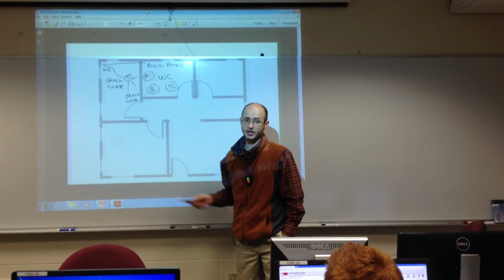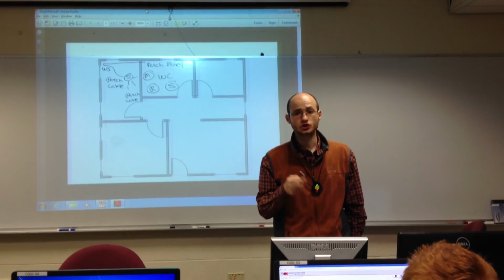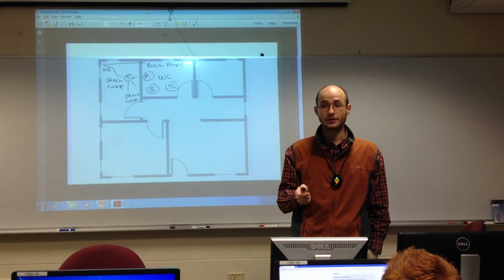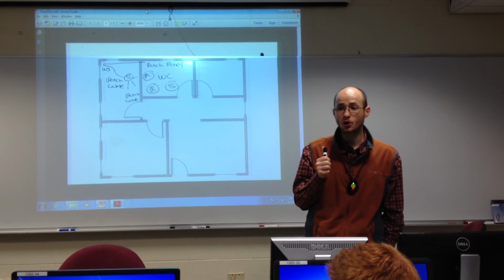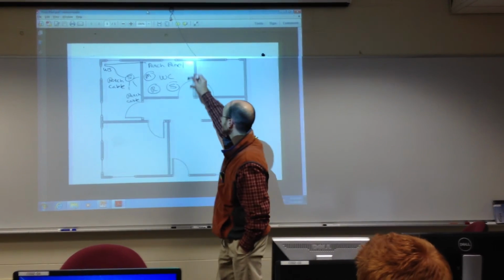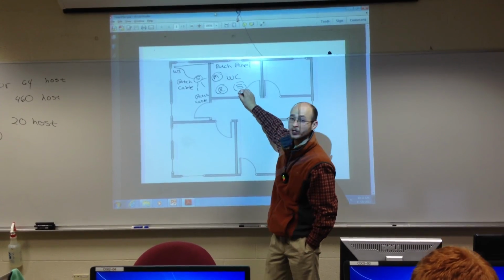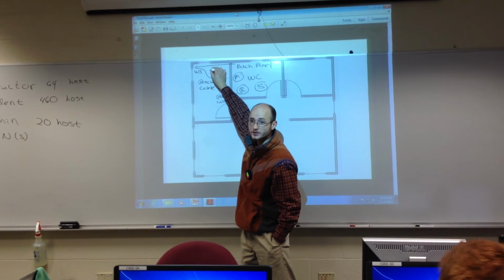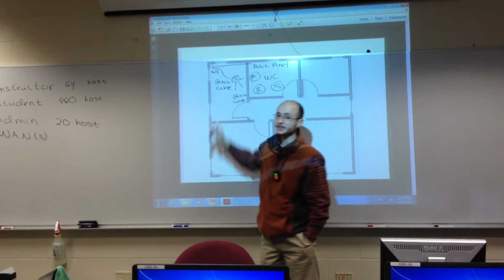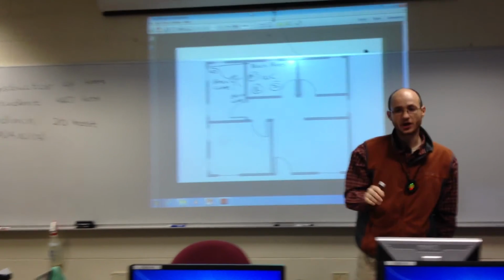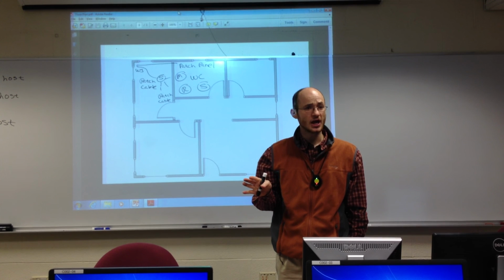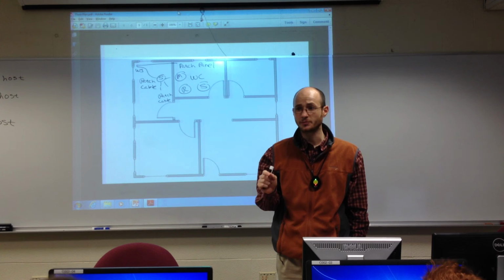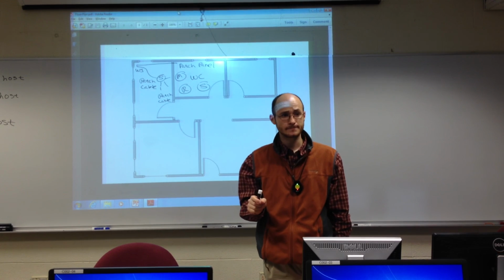So what do we gain by putting a wiring closet on every floor? Shorter horizontal runs. More work for us. Yeah, and it costs more. But short horizontal runs. The total length, that is the patch panel with the patch cable to your intermediary device, plus the horizontal run, plus the patch cable, has to add up to no more than 100 meters. So that's why we say the patch cable is no more than 10 meters, and the horizontal run no more than 80. Because 10 plus 10 plus 80 gives you 100 meters. Are we good with that?